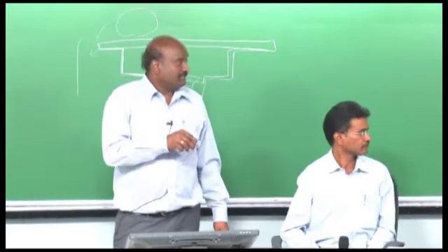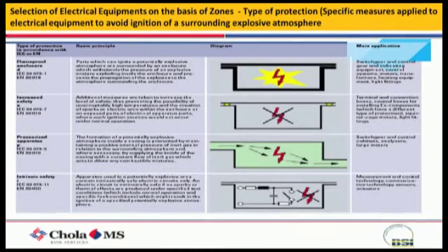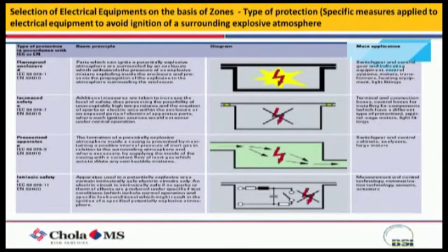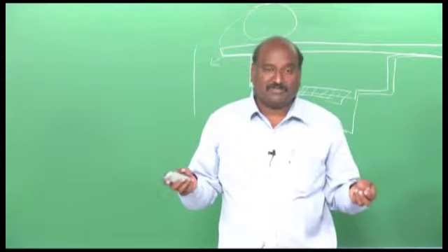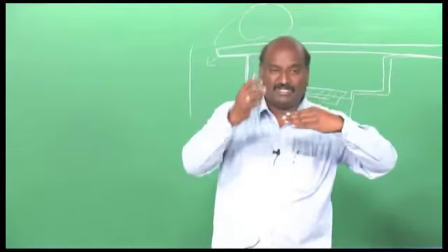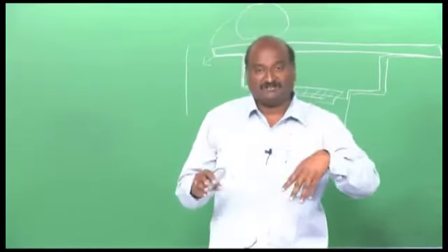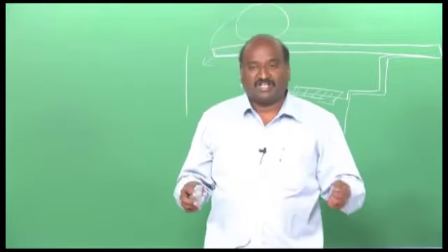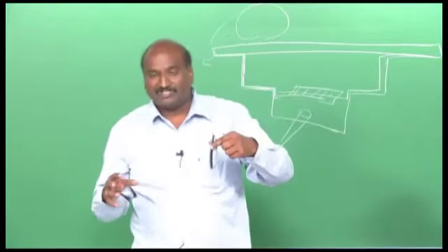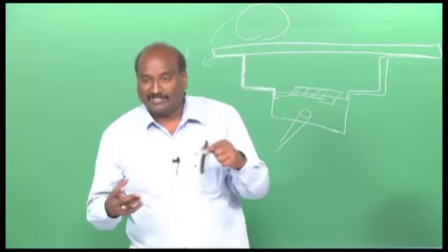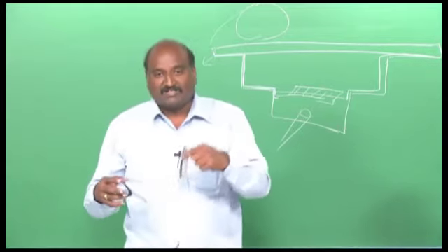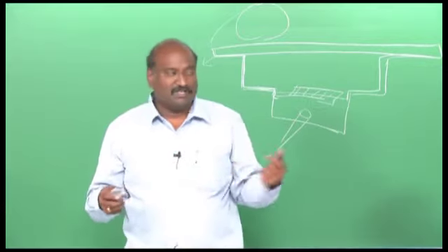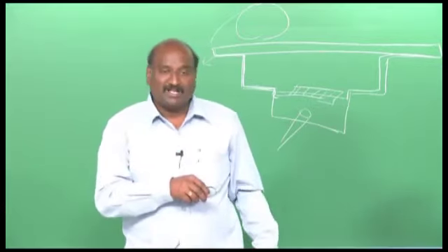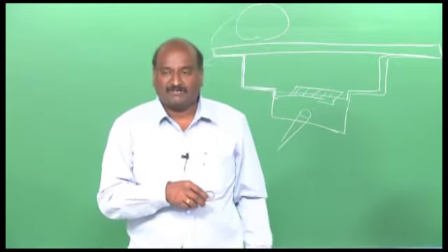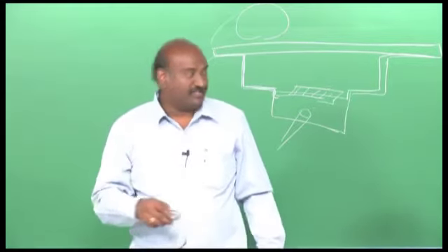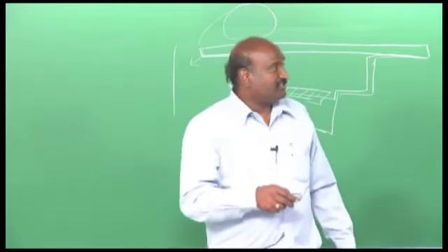This intrinsically safe type of instrument is used in zone 0 itself. As I mentioned, inside a tank there will not be any electrical instrument, but instrumentation like level indicators or temperature indicators can go inside the tank. Here there are Zener barriers which minimize the voltage to such low levels that it cannot create any explosion. Next is oil immersed.